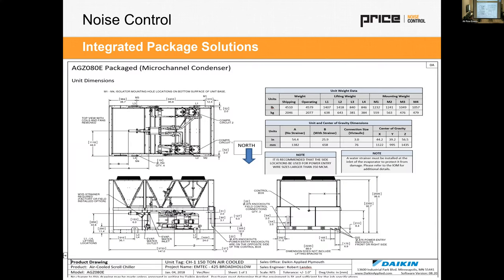One of the things that happens a lot is people go, oh, it's on an outside wall, I'll use an acoustic louver. Oh man, I can't get a lot of transmission loss out of an acoustic louver. Oh well, you can't do anything about it. And they forget that you can use a silencer. Yeah, or you can use both. Even a 12-inch deep louver doesn't give you that much insertion loss, whereas with a 2 or 3 foot silencer, you can get some pretty extensive insertion loss.